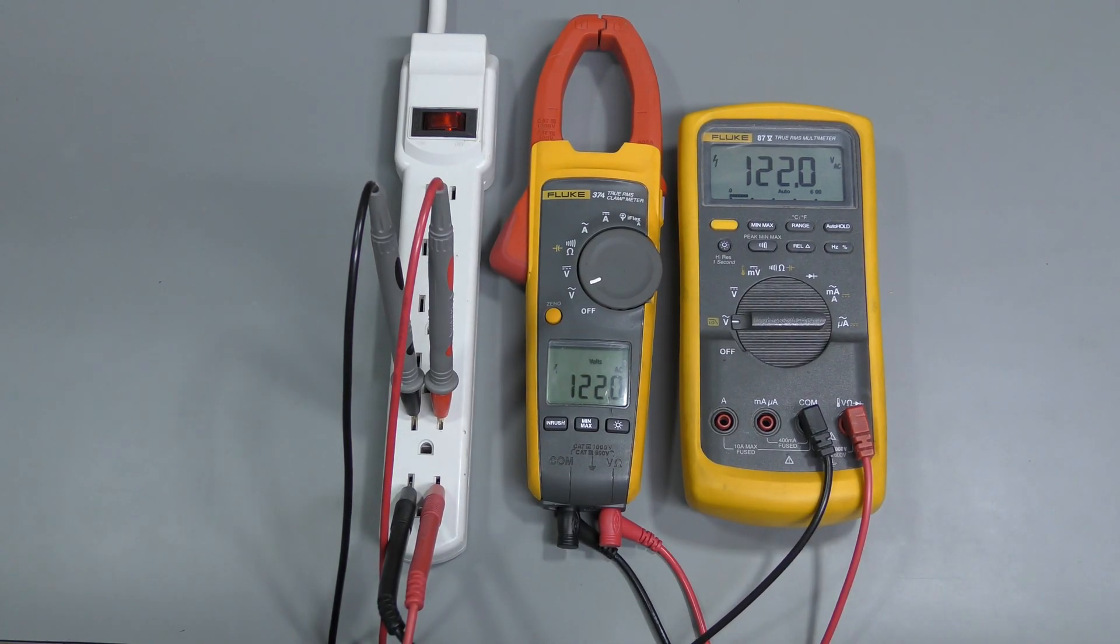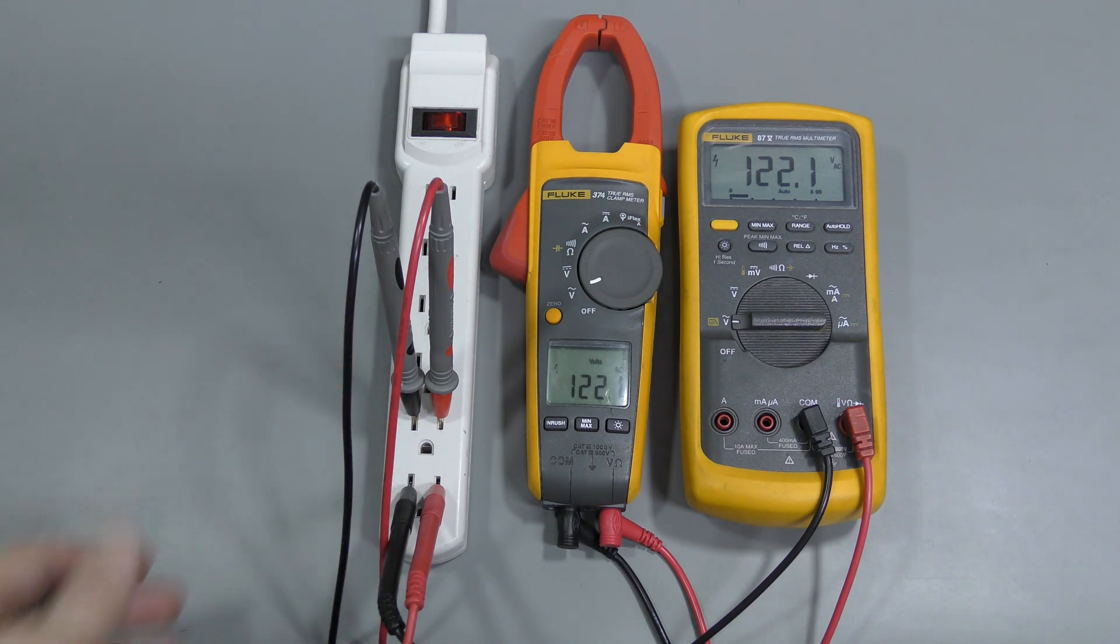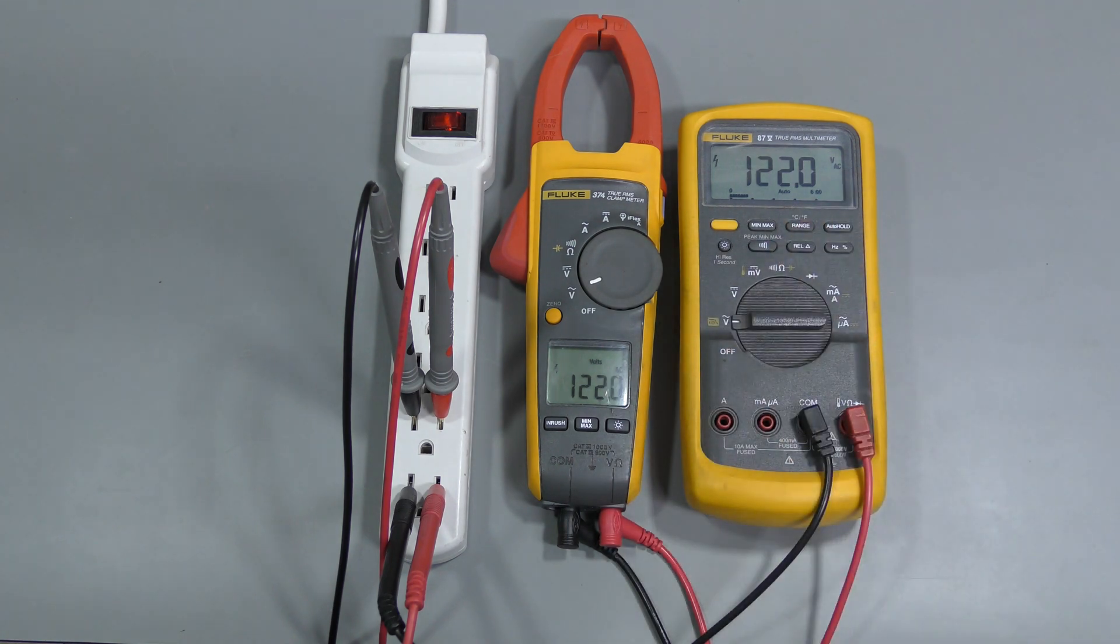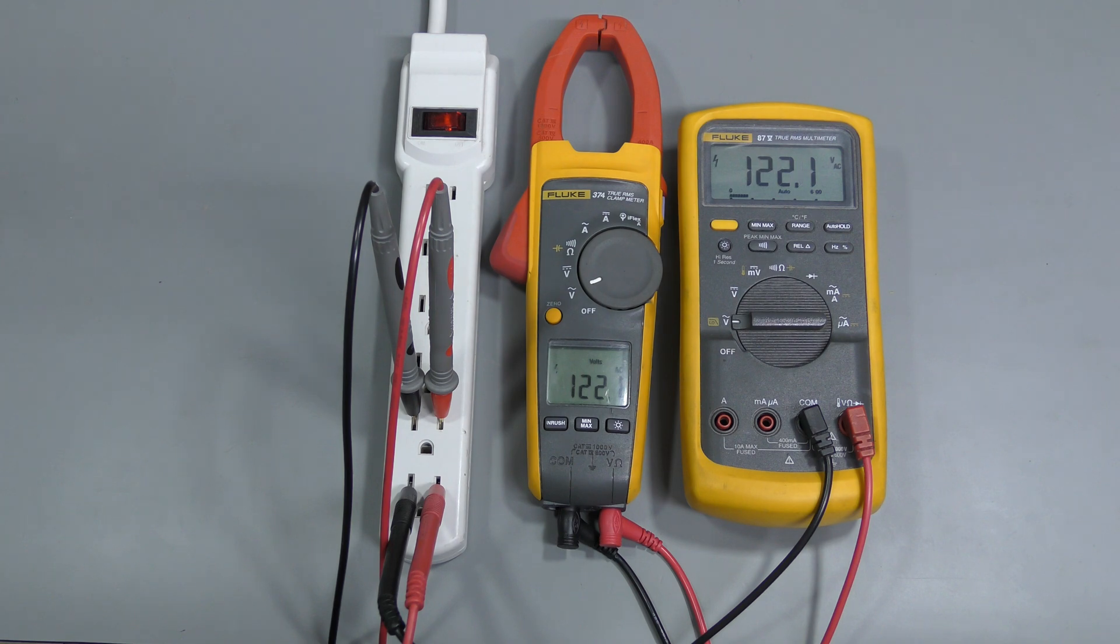I do not have an AC calibrator and we are just doing a basic checking anyway. So, let's just use mains and compare with Fluke 87, which is way more accurate than this clamp meter. And as we can see they agree almost perfectly.